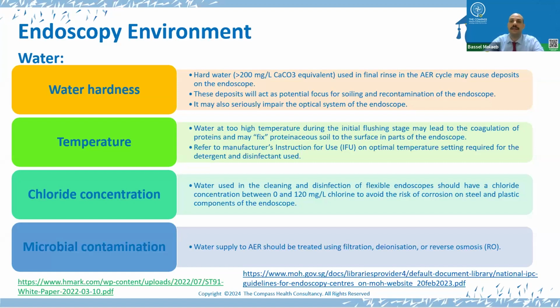In addition to that, the chloride concentration. Water that is used in cleaning and disinfection of flexible endoscopes should have a chloride concentration between 0 and 120 milligrams per liter to avoid the risk of corrosion on steel and plastic components of the endoscope. And lastly, microbial contamination. The water supply coming to the endoscopy unit, especially to the AER, should be treated using filtration and should be RO water.